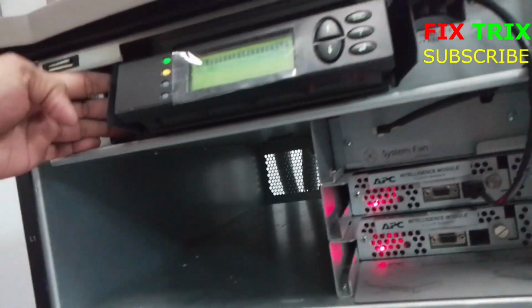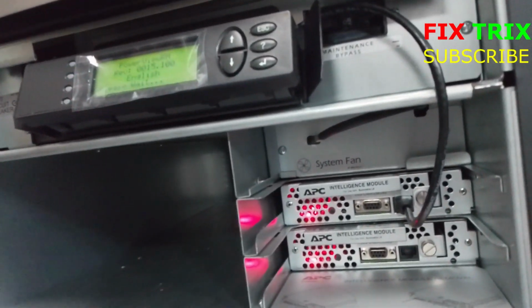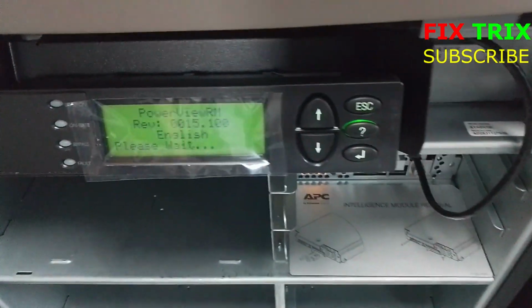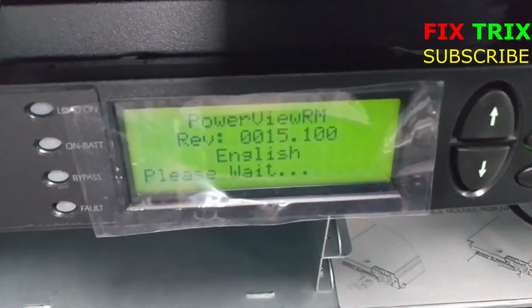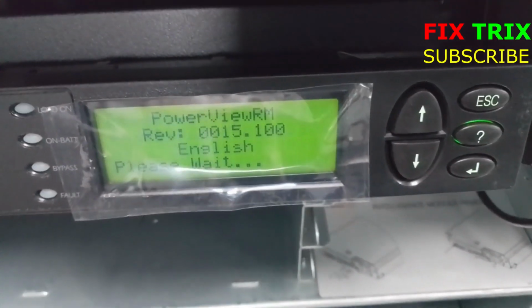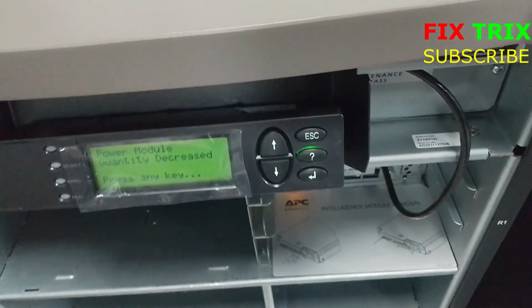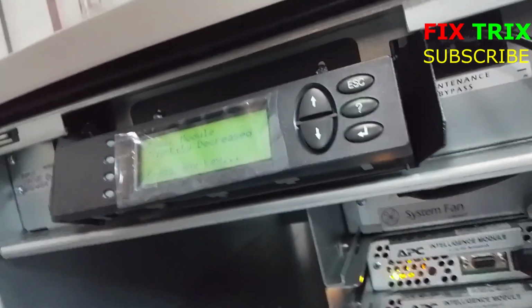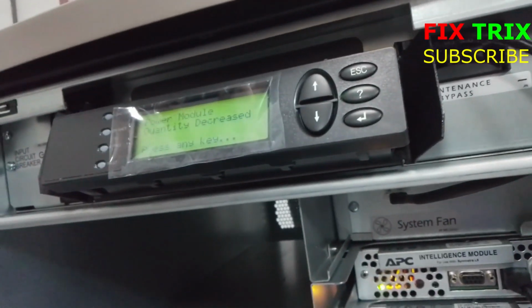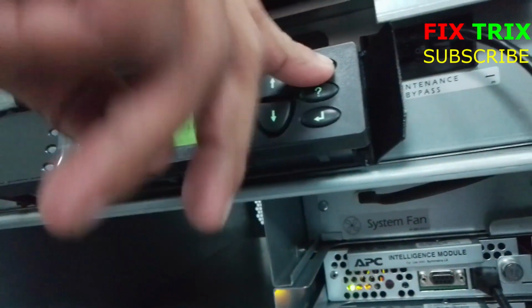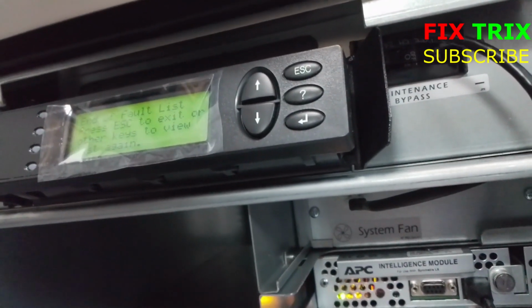After that we go to the back side of the UPS. Here you can see the system enable switch. Now we turn the system enable switch to on. This switch starts the UPS internal electronics. Now you can see the UPS display turning on. We wait and watch the display carefully to check system messages and status.